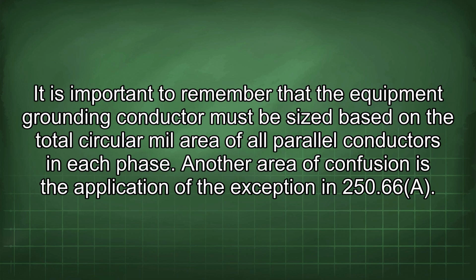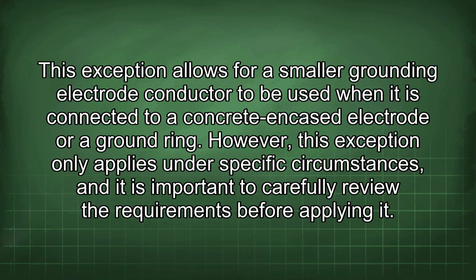Another area of confusion is the application of the exception in 250.66(A). This exception allows for a smaller grounding electrode conductor to be used when it is connected to a concrete encased electrode or a ground ring. However, this exception only applies under specific circumstances, and it is important to carefully review the requirements before applying it.